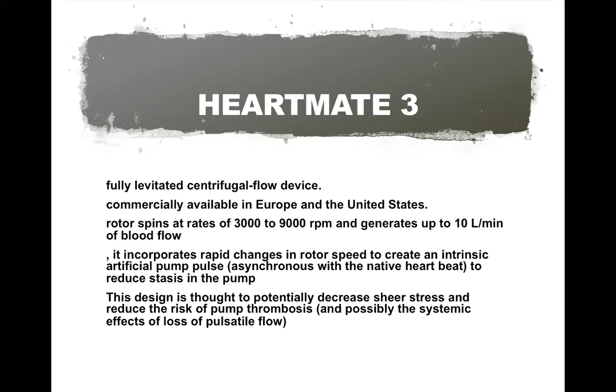So this is the new thing in HeartMate 3, where it has some kind of artificial pulse, asynchronous with the native heartbeat, to reduce stasis in the pump. And this actually resulted in better outcomes, with less pump thrombosis. This design is thought to potentially decrease the shear stress and reduce the risk of pump thrombosis and possibly the systemic effects of loss of pulsatile flow.